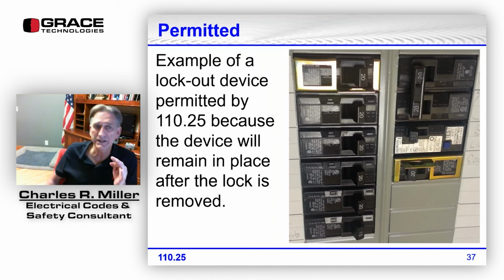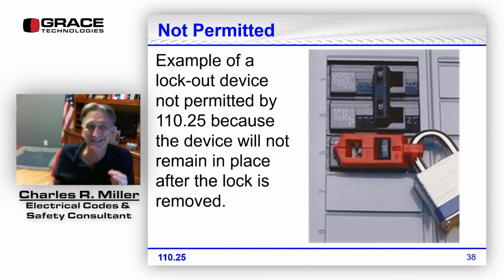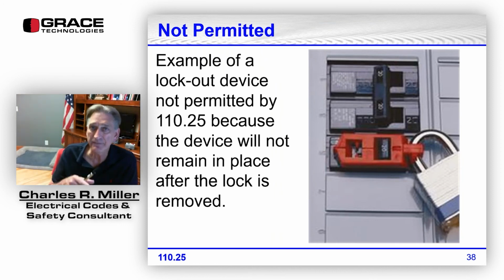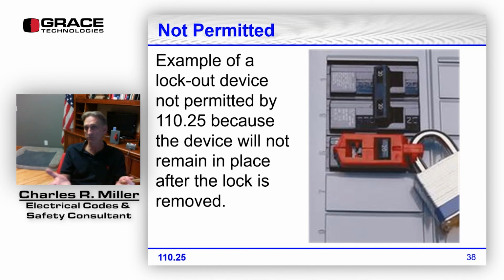All right, so here's an example of a device that is not permitted if it is required to have a lockout device on the circuit. This example is not permitted by 110.25 because this device will not remain in place after the lock is removed. In fact, you've got to remove the lock. You've got to take the plastic device off of the breaker in order to turn the breaker back on. All right, so probably what you're thinking is, oh, wait a minute.